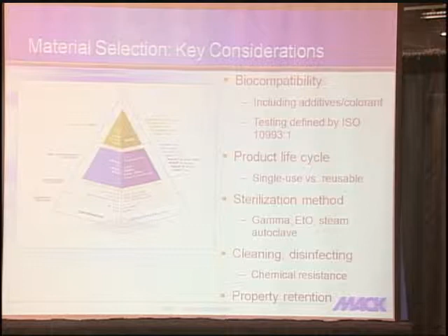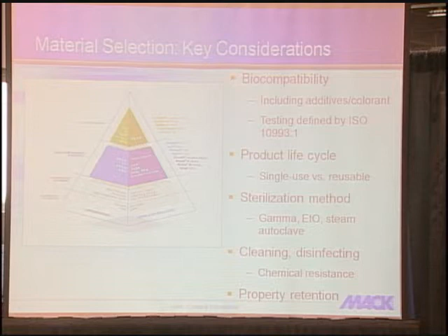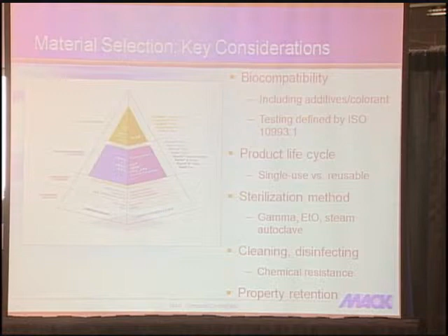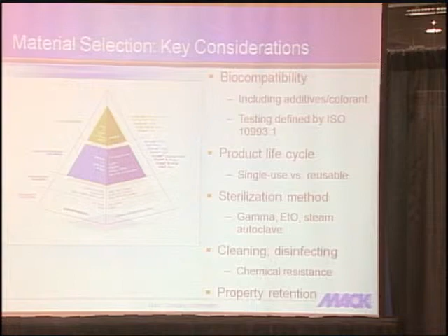And so some of the issues you want to look for are, is the material biocompatible? I mean, that's first off, if it's going to come in contact with the patient, tissue or fluids, it needs biocompatibility, typically ISO 10993. Is the product going to be disposable or reusable? So what is that going to entail on the material? Which sterilization method you're going to use? Gamma for typically disposable applications, to steam autoclave for reusable components. If it is reusable, most of the time you have cleaning and disinfectant issues to deal with. How's the chemical resistance in the material? How is that going to affect part performance? And finally, what is the property retention? For reusable devices, this is pretty critical because the part will have to go through multiple cycles.